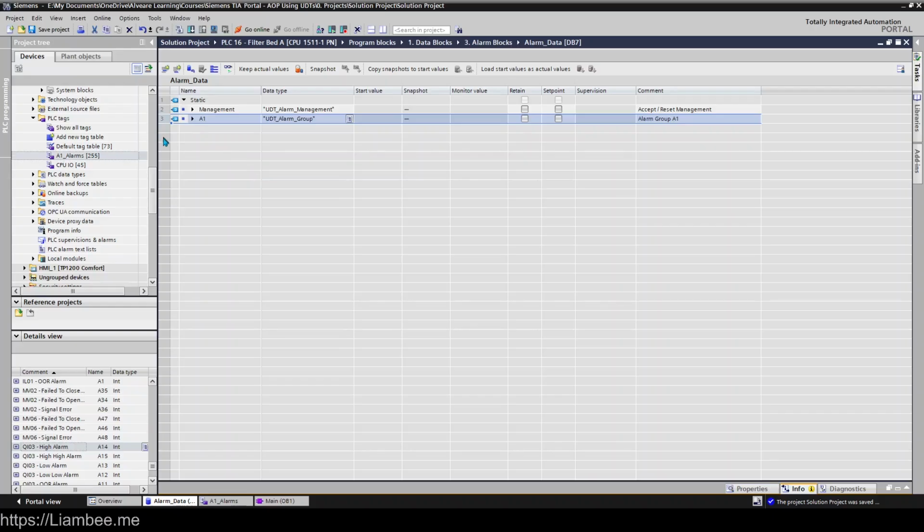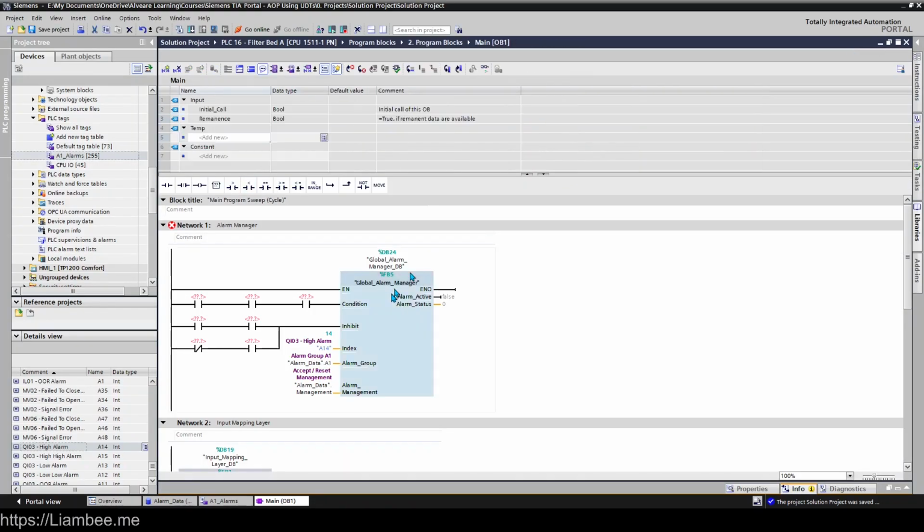So you might decide that you want 4 groups because you often use up to 4 groups, and that would be acceptable. You could standardize that, and you'd have to take the hit on the wasted groups if you're not using them. But it makes a lot more sense in something like this to just have a data block and then pick the group that you're raising an alarm in, because it's unlikely that you're going to have multiple alarms with different indexes in different groups that need to be raised at the same time off the same condition.